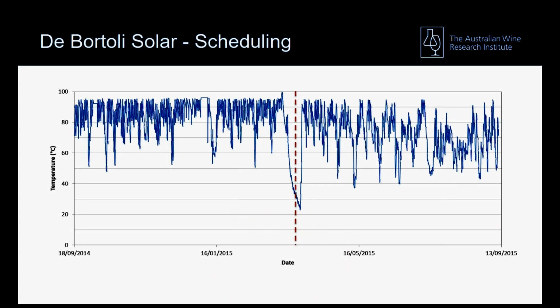Another thing to consider in making use of solar is your scheduling of operations, having a well enough even flow to make use of the solar as it's generated. This graph shows the temperature in the storage tanks of De Bortoli's hot water system. On the left, all that time spent up at 95 degrees meant their tanks were holding all the heat they could, and they weren't able to draw any more heat off the roof. So they rescheduled a number of their cleaning and heating operations and changed some control systems, and now, on the right-hand side, they're spending much less time at that 95-degree peak. Scheduling your operations to use the heat as it's generated is really important to get the most efficiency out of your system.